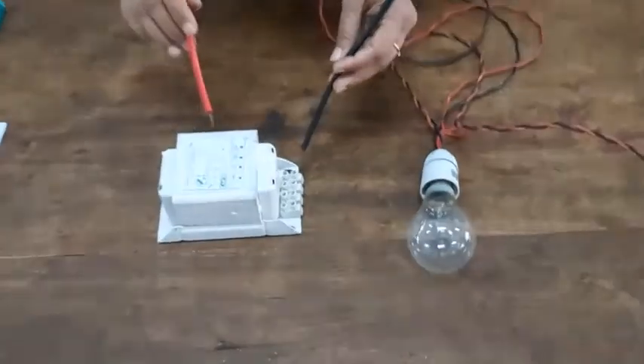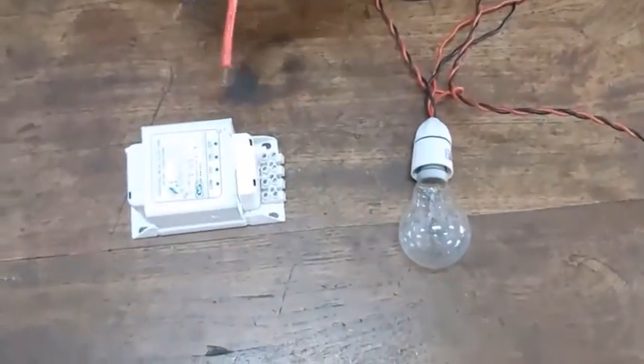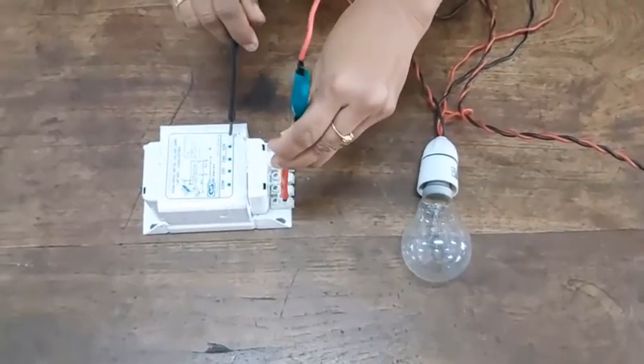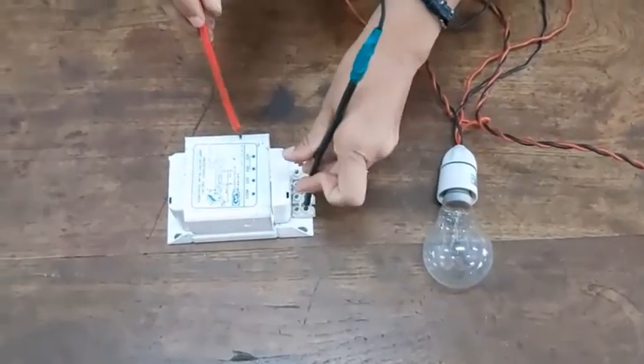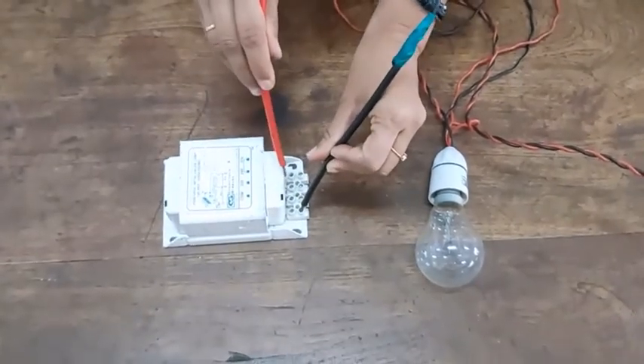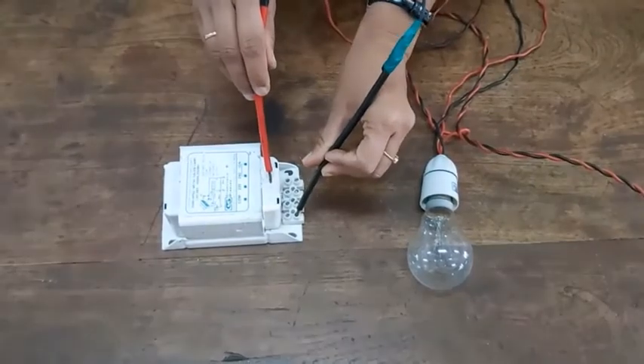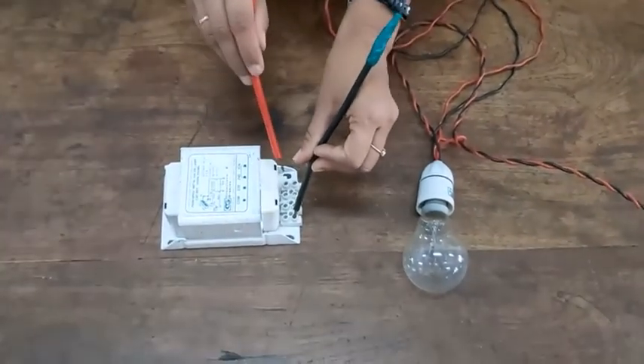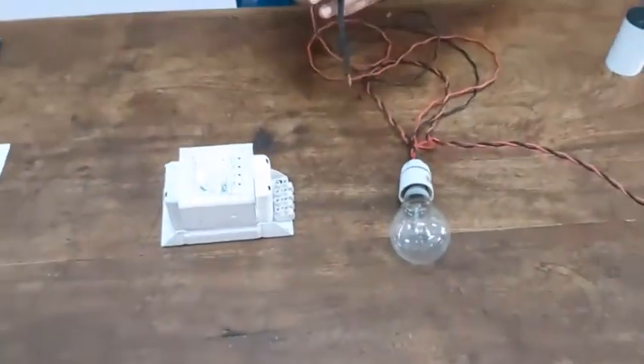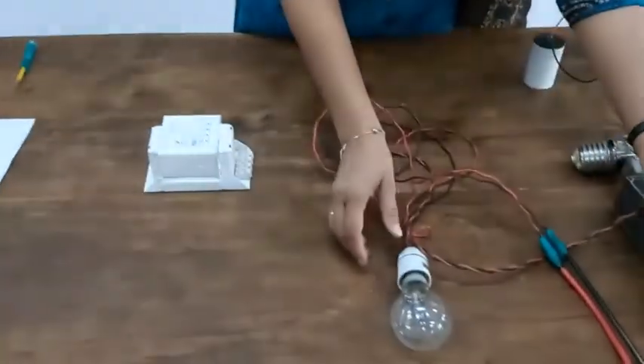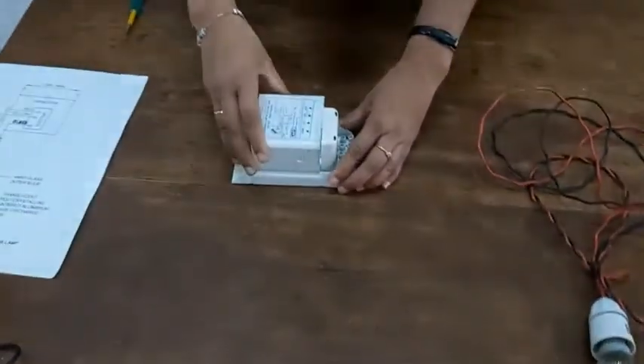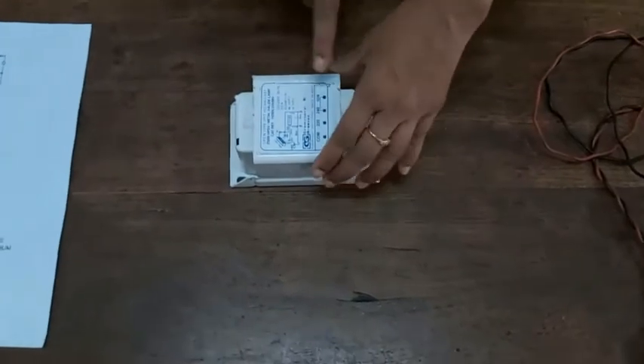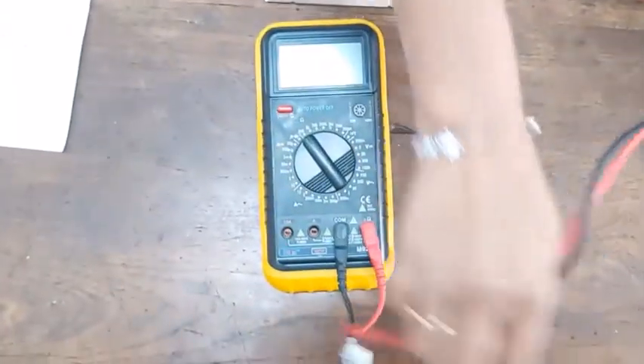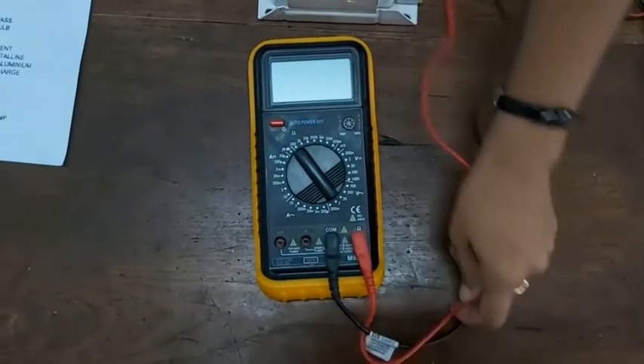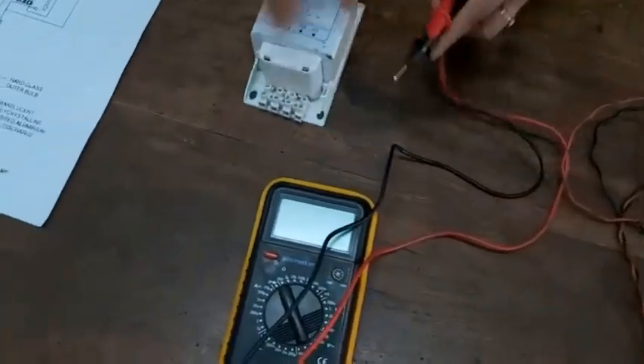Now I am going to do the ground test for this choke. So the series test lamp is in off condition. This shows that there is no ground fault in the body of this choke. Now I am going to measure the resistance for checking the short circuit fault in this choke using a multimeter also. So here I am going to measure the resistance value of this choke.